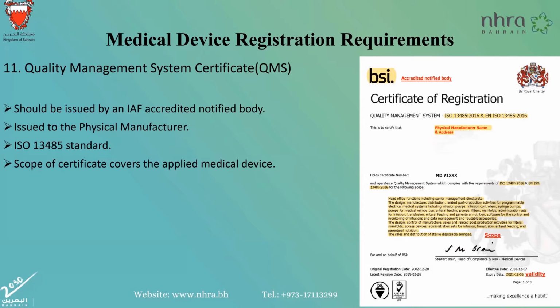Previously, for low-risk medical device applications where the CE is not required, the quality management system certificate was required to be valid for at least 1 year, but now we have cancelled this. So it just needs to be valid in all cases.